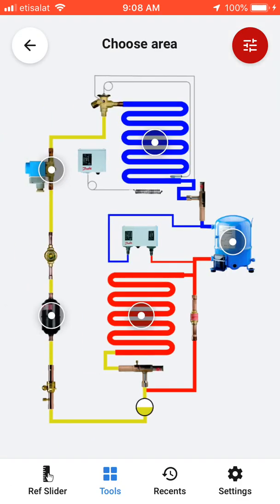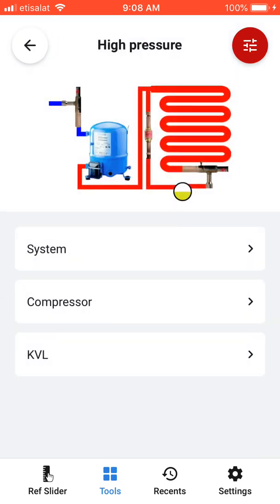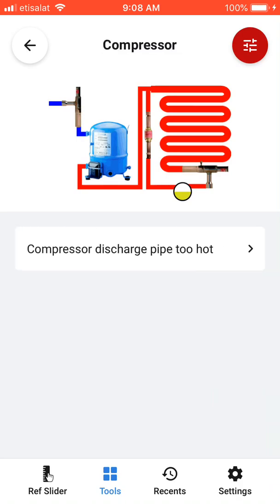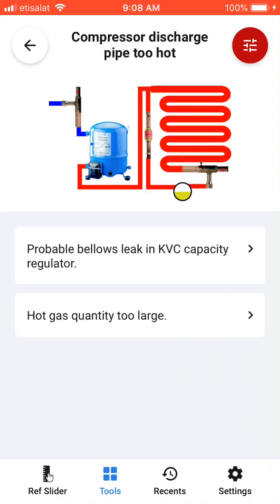You can also select the high-pressure side of the refrigerant cycle — the compressor and condenser. For example, if there is a fault in the compressor, such as the compressor discharge pipe being too hot, there are two possible reasons: a leak in the KVC capacity regulator, or the hot gas quantity being too large.